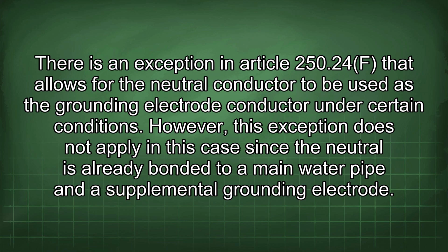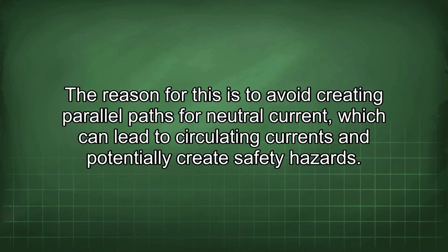There is an exception in Article 250.24(F) that allows for the neutral conductor to be used as the grounding electrode conductor under certain conditions. However, this exception does not apply in this case since the neutral is already bonded to a main water pipe and a supplemental grounding electrode.